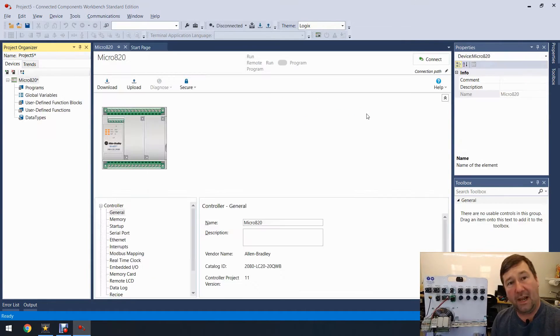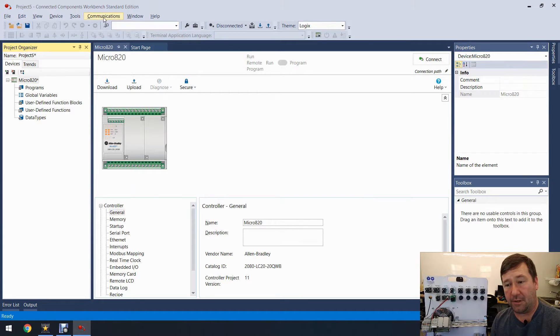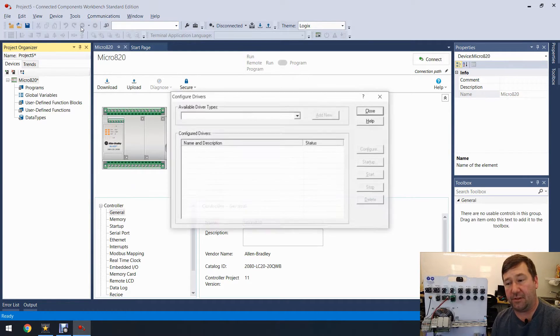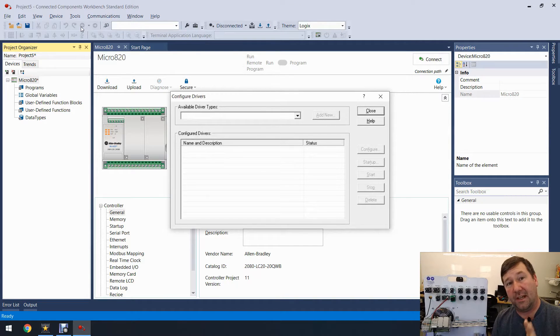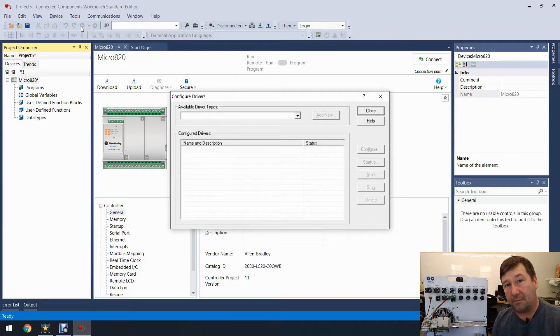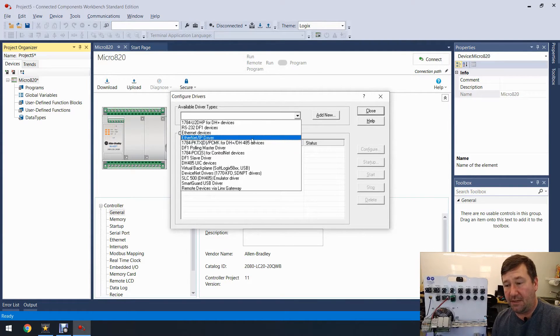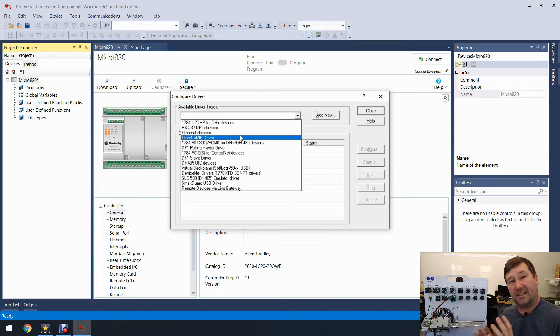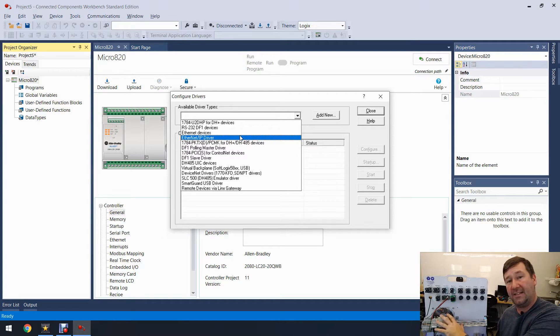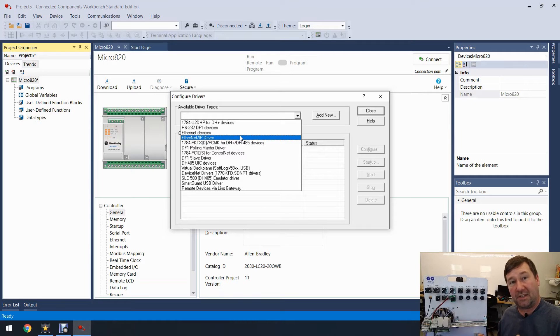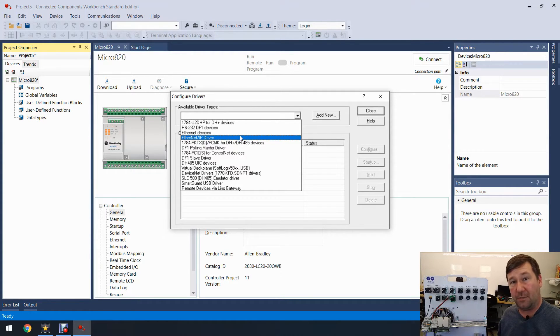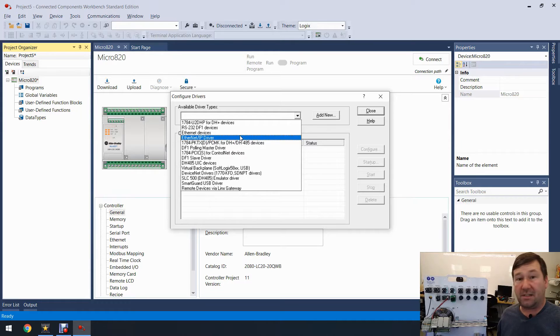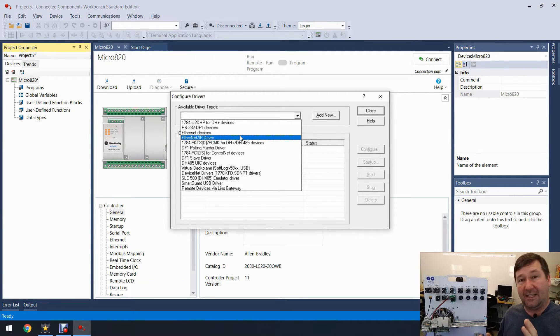Now we're going to configure our ethernet driver. To do that we're going to go to Communications and Configure Drivers. There are actually two ethernet drivers and they both have a very important purpose. First you have the Ethernet/IP driver and what it does is it listens for broadcast packets that are coming from the PLCs to discover devices on the network. This is really useful especially when you're unfamiliar with the network that you're on, but some firewalls and advanced routers will block these packets.